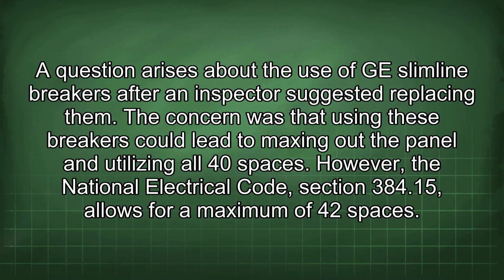A question arises about the use of GE Slimline breakers after an inspector suggested replacing them. The concern was that using these breakers could lead to maxing out the panel and utilizing all 40 spaces. However, the National Electrical Code, Section 384.15, allows for a maximum of 42 spaces.